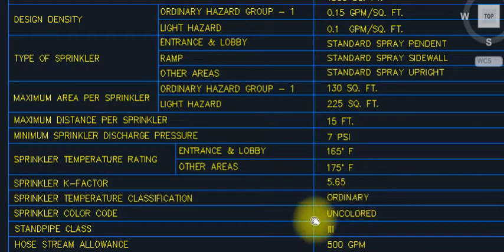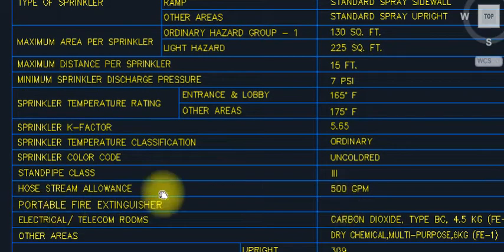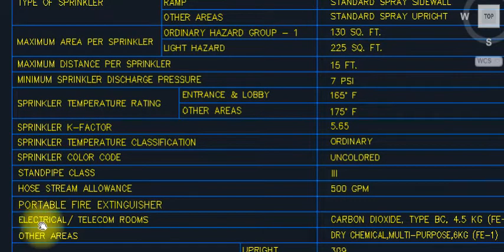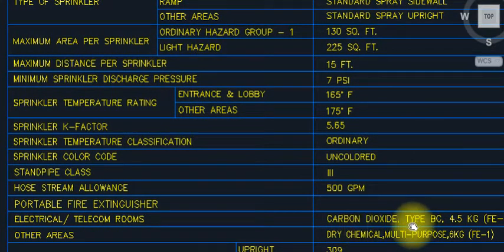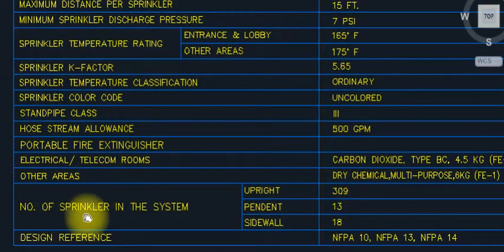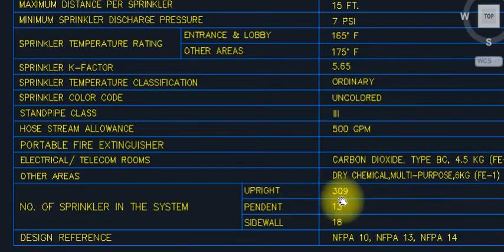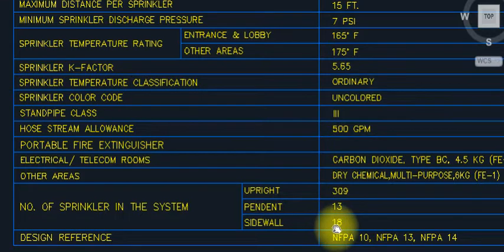Temperature classification for ordinary sprinklers. Hose stream allowance: 500 GPM, standpipe class 3. Portable extinguishers included. Electrical and telecom rooms: carbon dioxide — now FM200 and Novec systems. Other areas: dry chemical multipurpose extinguishers. Sprinkler quantities: pendant type upright in parking area — 309 upright, sidewall 18. Sidewall sprinklers are always used in the ramp area.